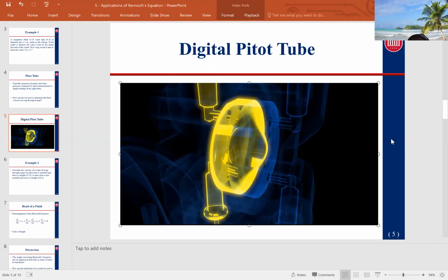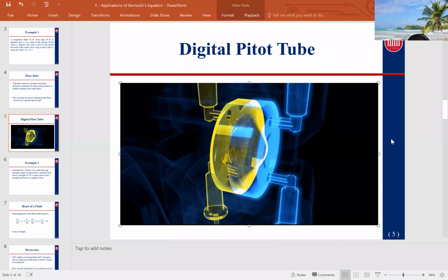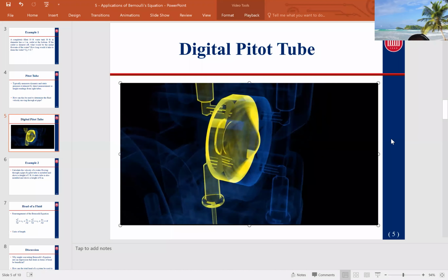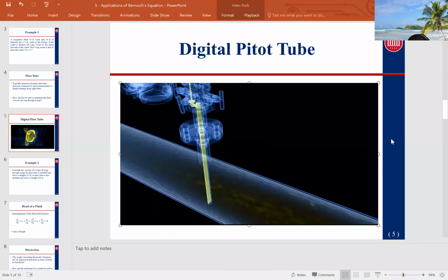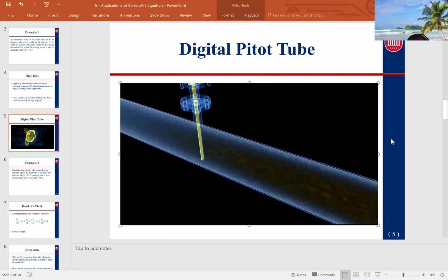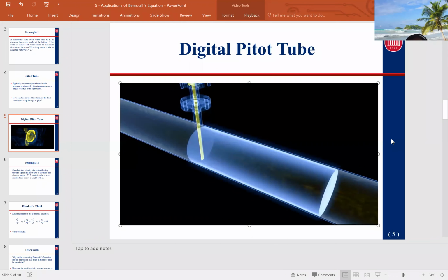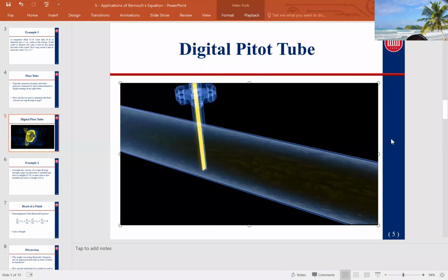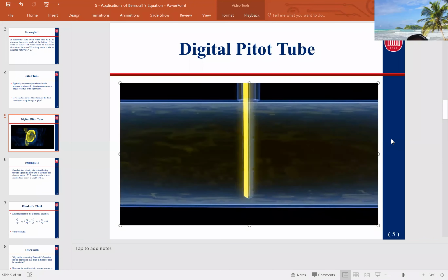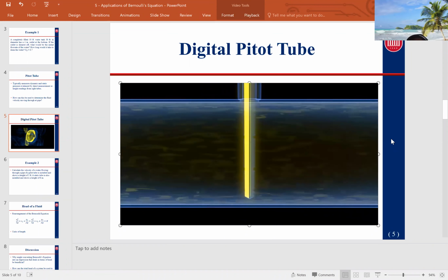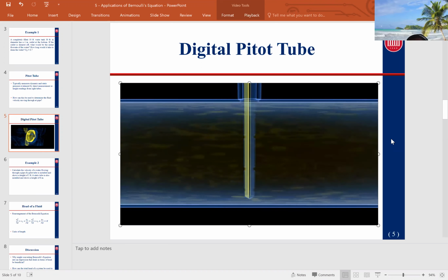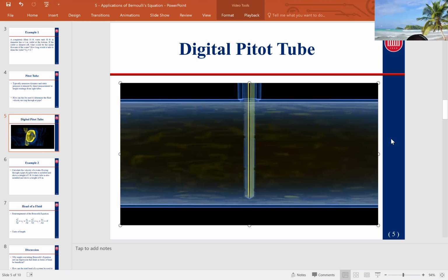Higher pressure against the flow and constant pressure on the rear of the Pitot tube. This pressure difference is a direct measure for the flow velocity and thus the mass and volume flow in the pipe. The higher the flow velocity and therefore the dynamic pressure, the greater the differential pressure measured. Pitot tubes are able to register the flow in both flow directions. This means that balancing measurements, for example in gas pipeline networks, can be carried out at any time.